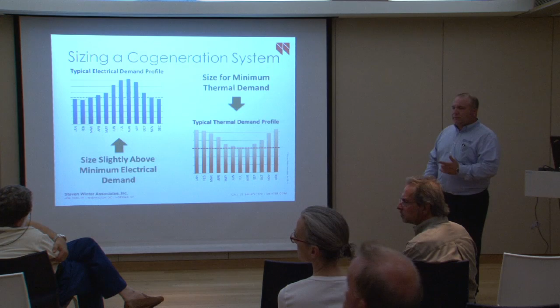For the cogeneration system, how do you size for the maximum peak demand? In certain situations, NYSERDA allows us to size for peak demand. It depends on the building, since economic factors drive that decision. The benefit is the system can give the building full backup capability in certain load situations. All of this depends on other factors like space and how the building is wired.